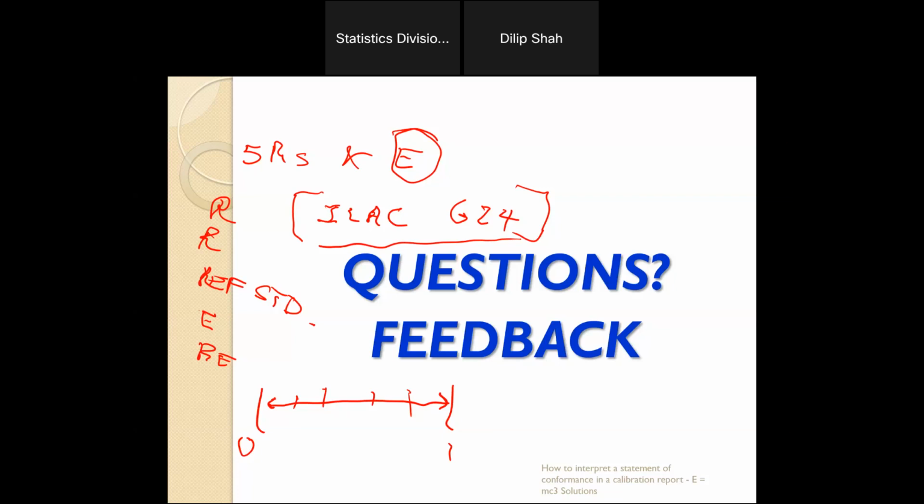He would tell you, yeah, it's 5 months, 2 days, and 3 hours. But they had the population to do the appropriate statistics. A lot of times, smaller organizations and even larger organizations don't have that large population of one make and model of that instrument to do that determination.